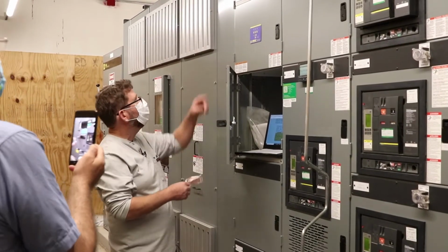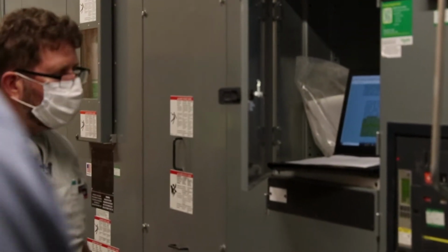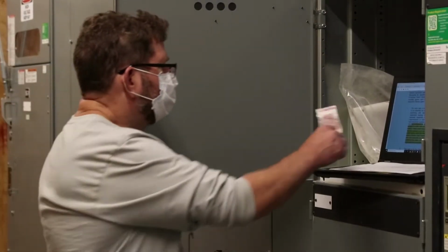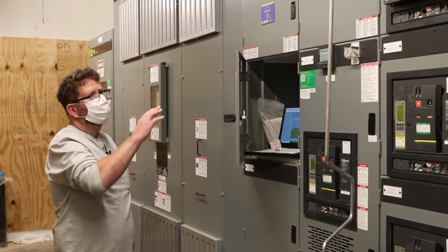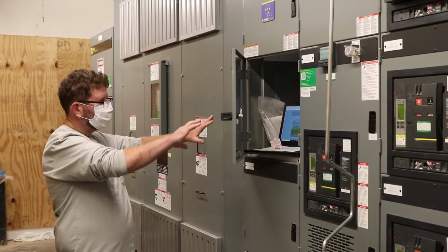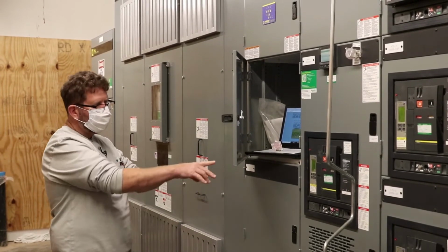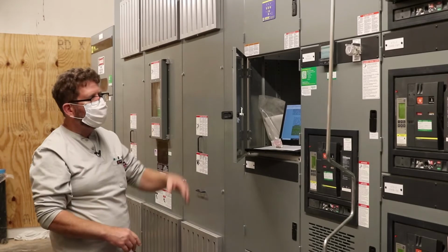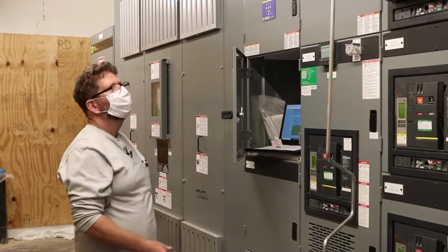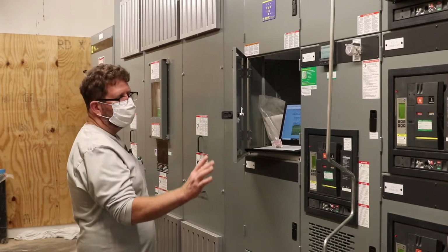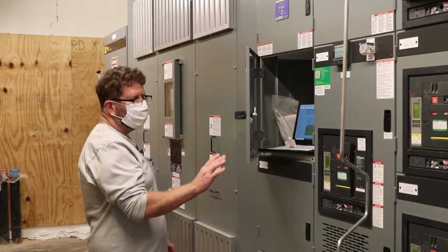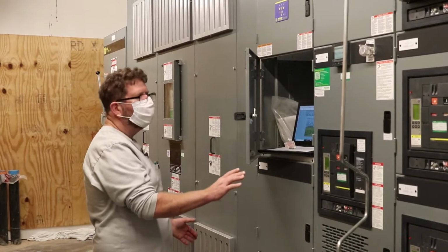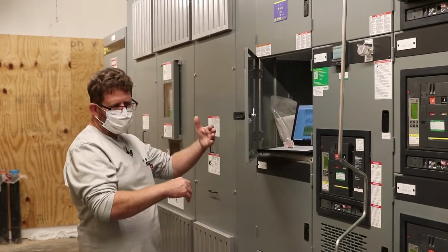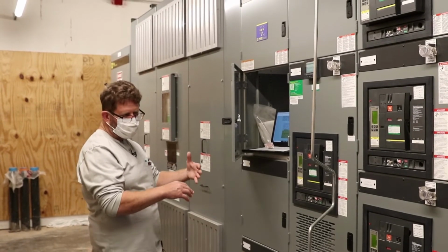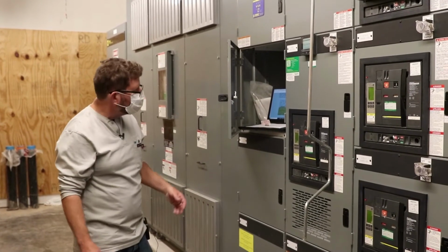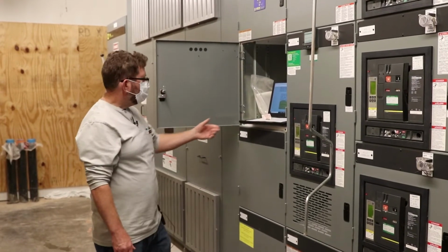Move down to what we call PZ4, Power Zone 4 style switchgear. It's 480, 277. It's built to be compartmentalized sections. You have the front section of the gear where you're going to find the breakers, control components, metering, communication. Then behind the front section is the bus compartment. Bus compartment is not accessible through the front at all. If you come in through the back, you'll see the first thing you get to is a cable compartment, and then the bus compartment is isolated.